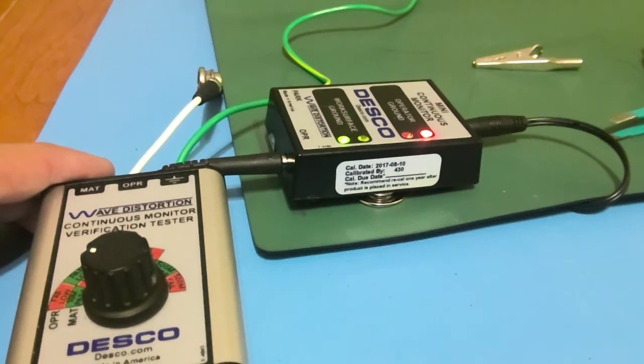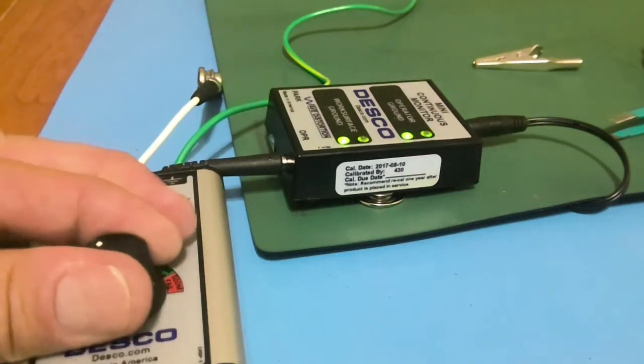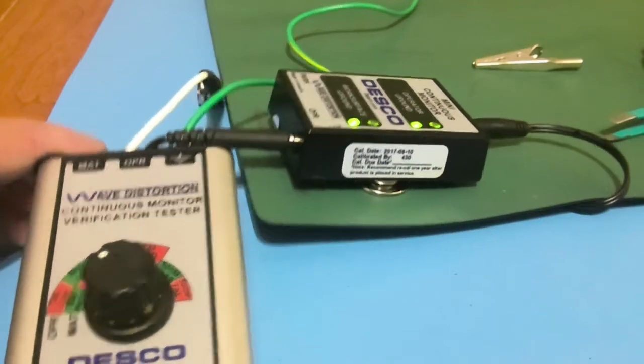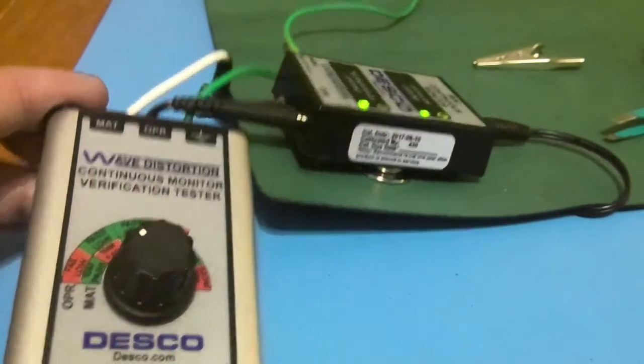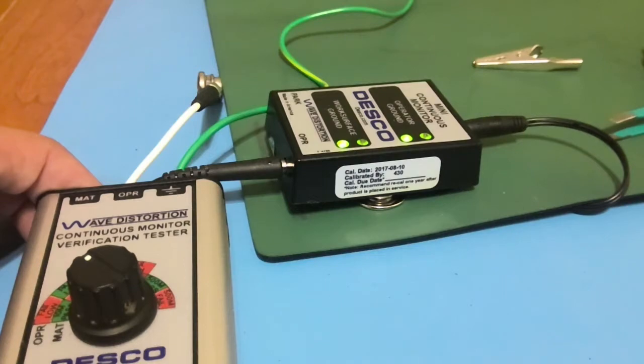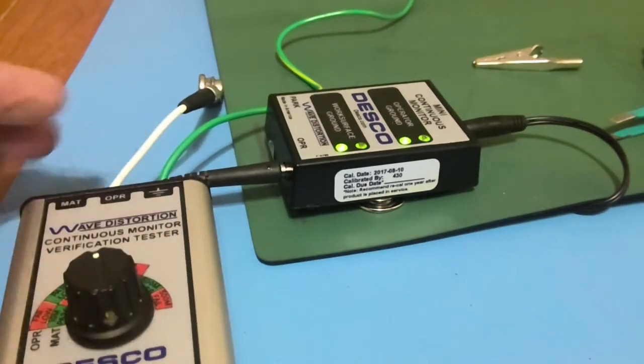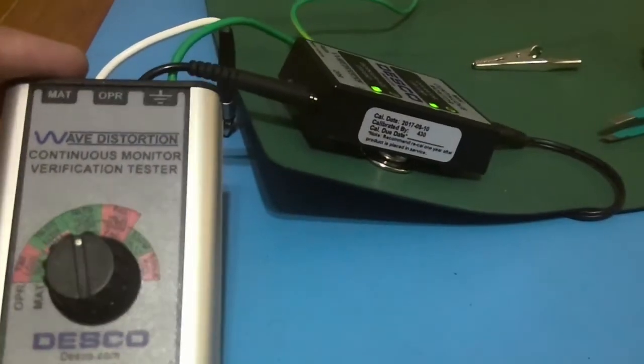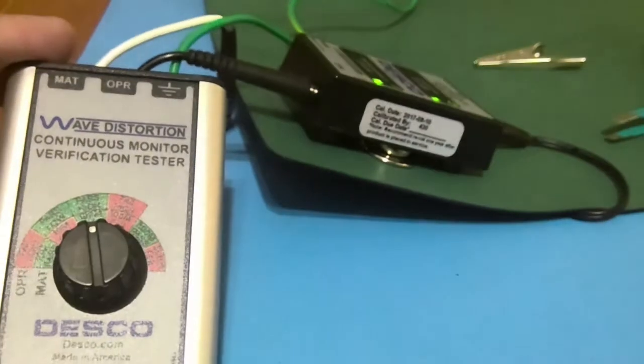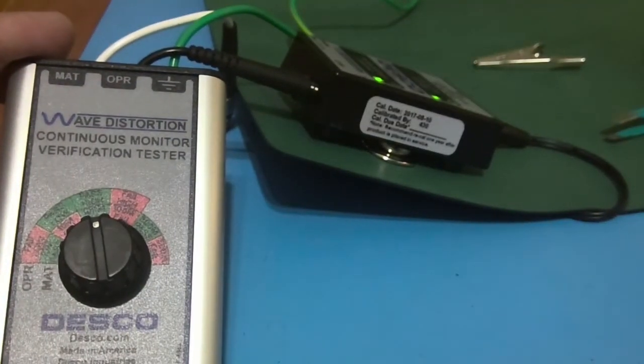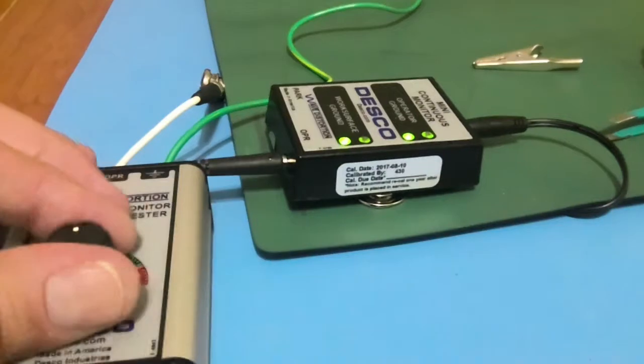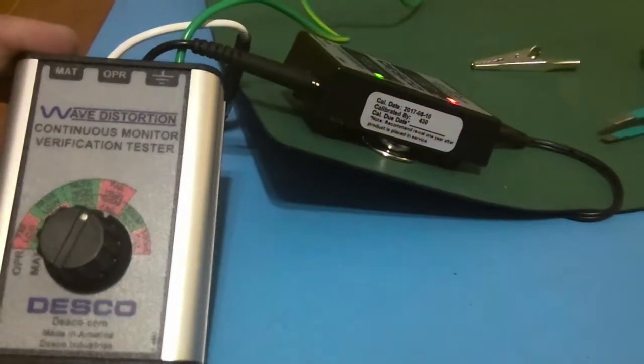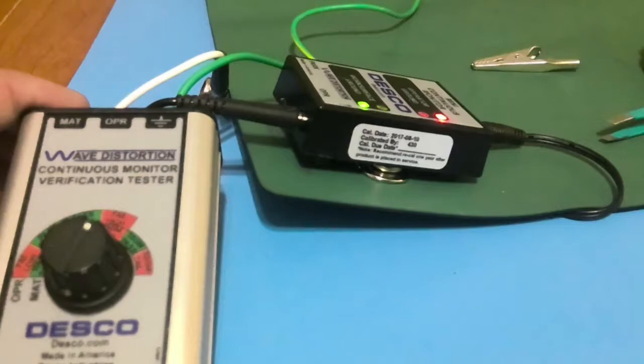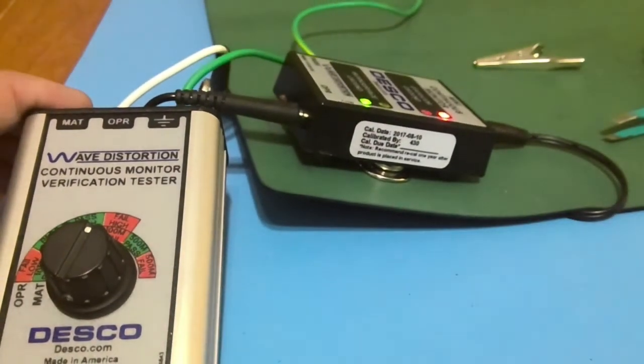Okay, close enough. So we're going to take this dial all the way to operator fail low, and you'll notice the monitor is saying that there's a fail condition. The next one is pass low, got a green light, that's good. We go to the next one, which is pass high. You can see that right there, pass high. And the last one is the red, which is fail high. So that completely tests the wrist strap circuit. You're good to go for that.